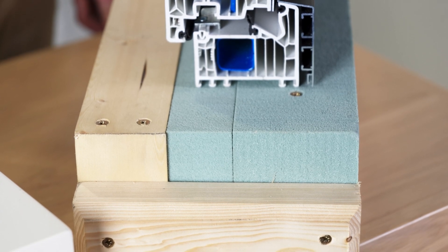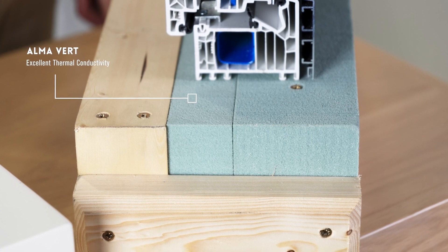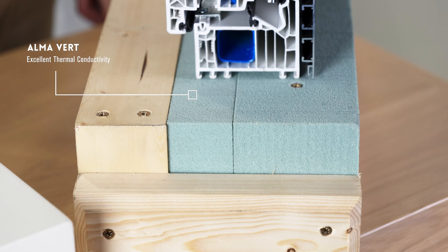The 115 kg density panel has an excellent thermal conductivity of 0.036 or 3.43 R value per inch. Despite being a structural solution, the insulation values for this product are very similar to many traditional insulations.